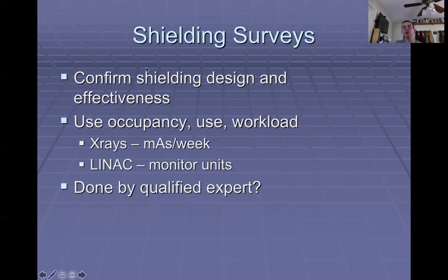So we need to take these dose rate meters. Anytime a new machine goes into a LINAC vault, anytime a new LINAC vault is built, we run up, down, left, right, and anywhere that anybody could physically place themselves around these vaults, we will take dose rate measurements to make sure that there are not any excess levels of radiation that could be out of compliance or just a general hazard.